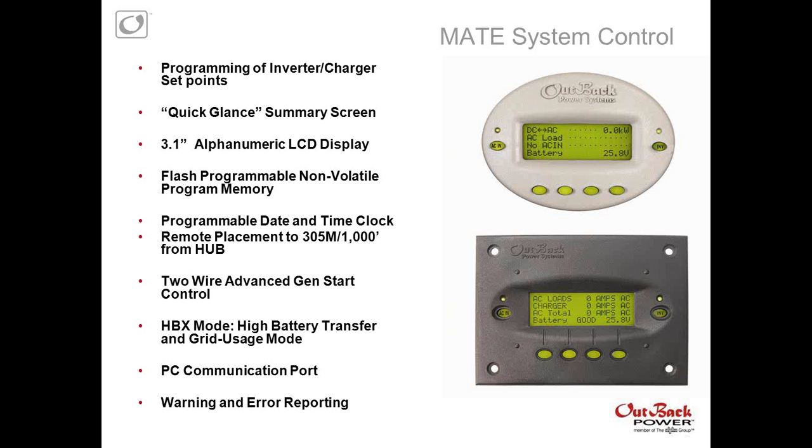You know, the good thing about the Mate is the unlimited functionality. It has over 480 screens to be used with the programming. You can set up anything from battery types, battery and charging profiles, automatic generator starting, really unlimited capability. But also the bad part of the Mate as well is it has over 480 screens to learn. And that's one of the real limitations of this unit.